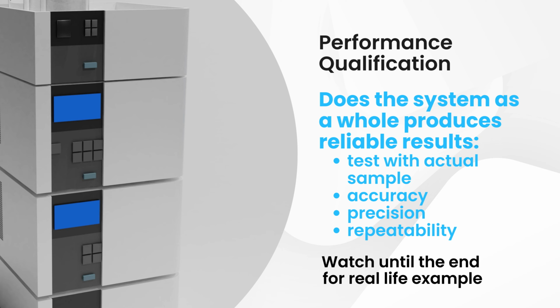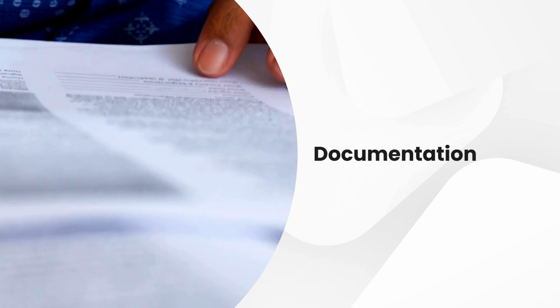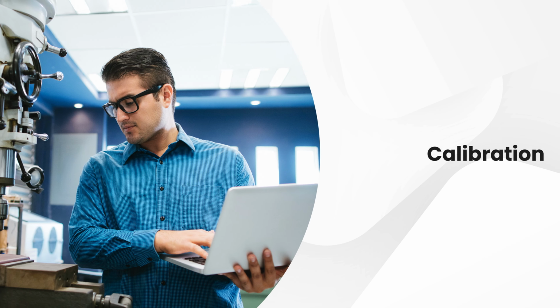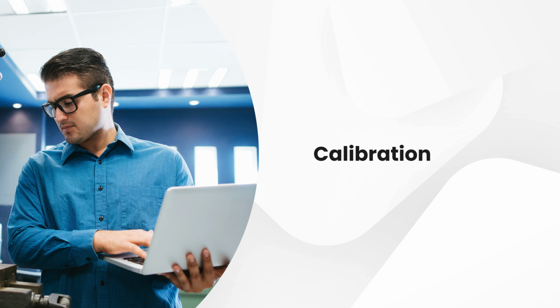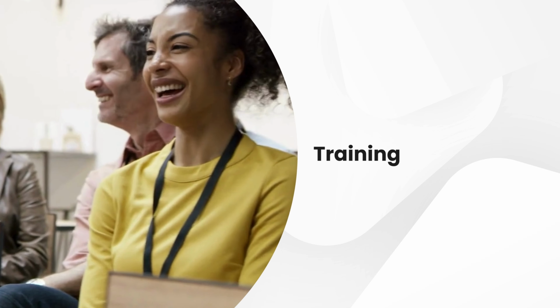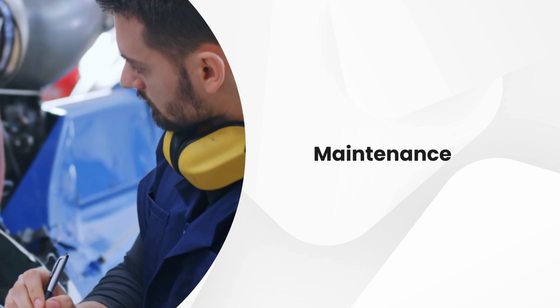Key considerations for successful HPLC qualification. Documentation. Meticulous record keeping is essential. Document every step of the process, including protocols, results, and any deviations. Calibration. Ensure all reference standards and any measuring devices used in the qualification process are properly calibrated. Training. Personnel performing qualification must be adequately trained and qualified. Maintenance. Regular maintenance and preventive maintenance are critical for keeping the HPLC system in a qualified state.